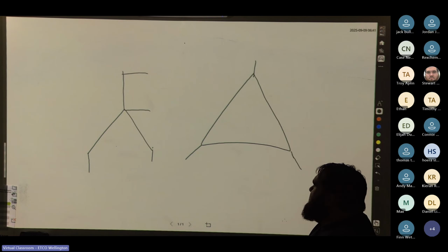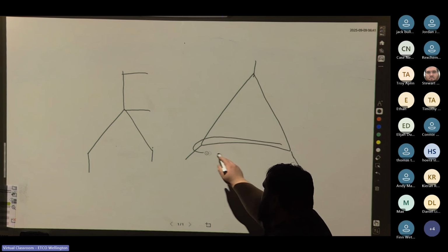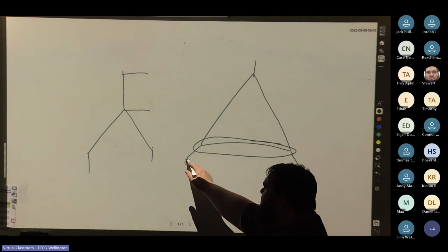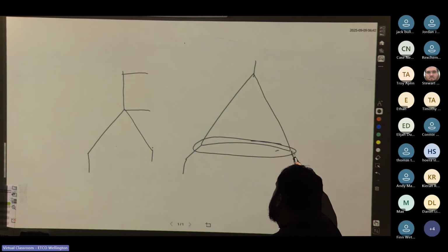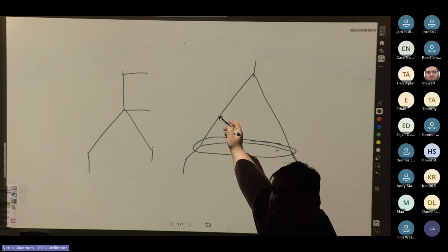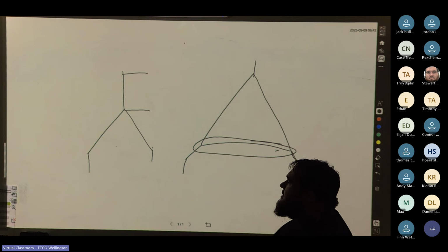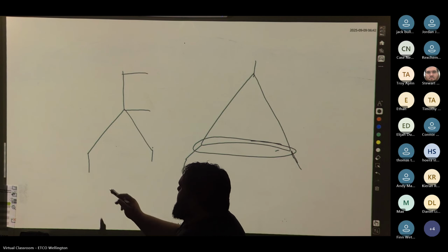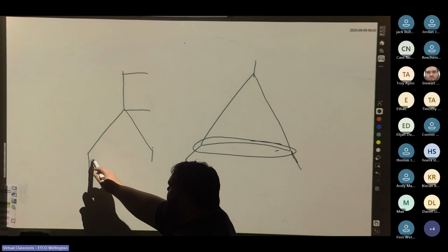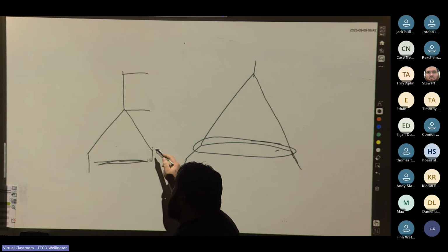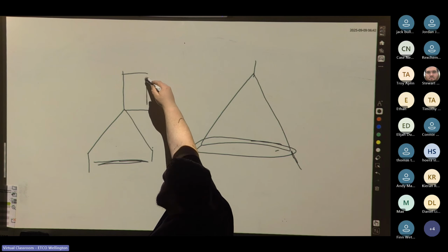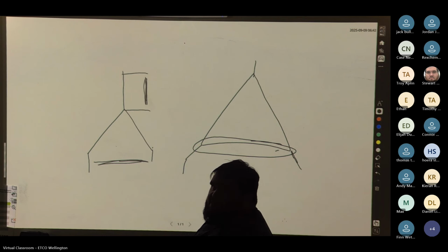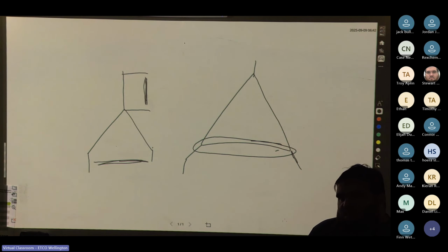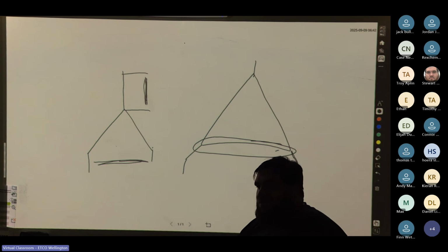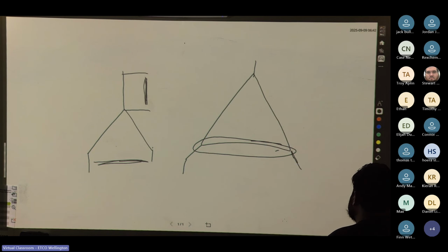So no matter where you measure this phase, you're always going to get 400 because it's always connected to the two other phases. So you're always technically measuring two phases. Whereas with star, I can measure between phases here, or I can measure between phase and neutral. So my phase and neutral is going to be 230. And again, we will talk about that relationship in a little bit.